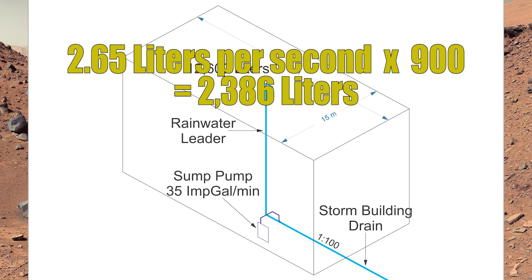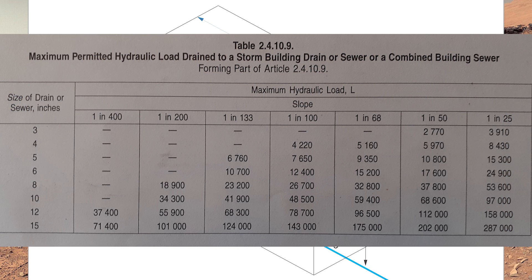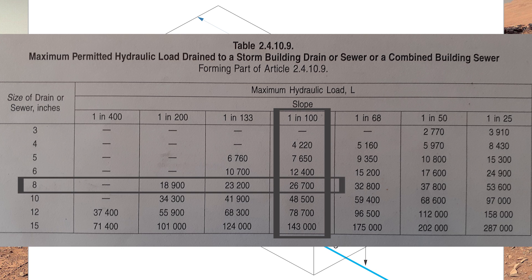To size the storm building drain that has both the rainwater leader and the sump draining into it, we add those two numbers together: 12,600 liters plus 2,386 liters equals 14,986 liters, graded at 1 in 100. Back in table 24109, going down the 1 in 100 column up to 26,700 — that is also 8 inch.